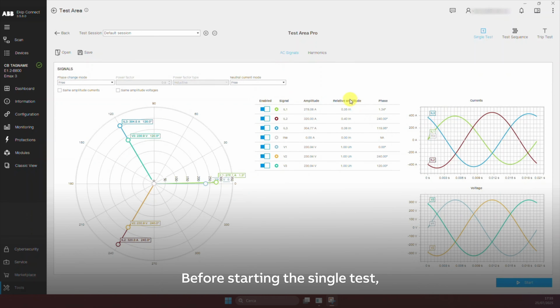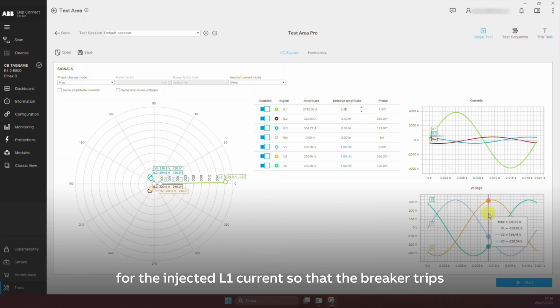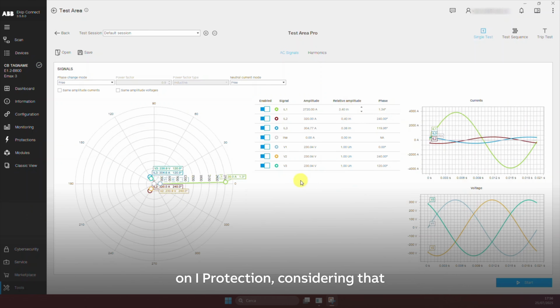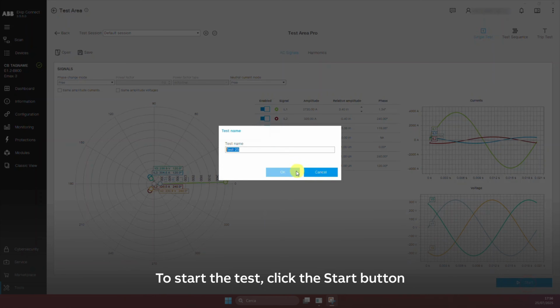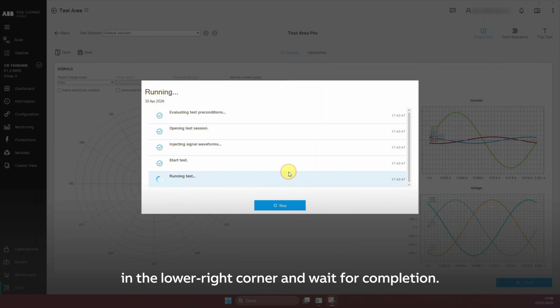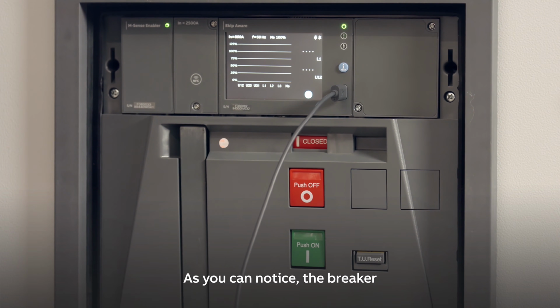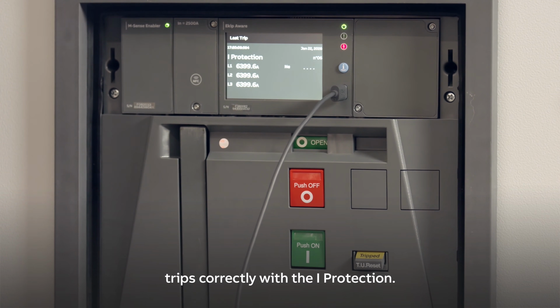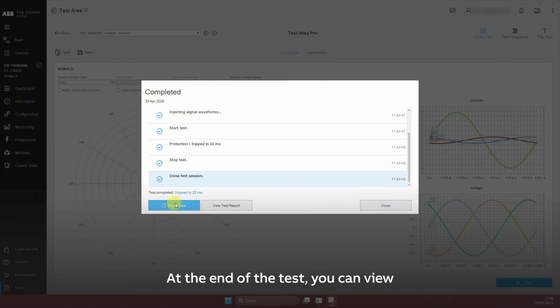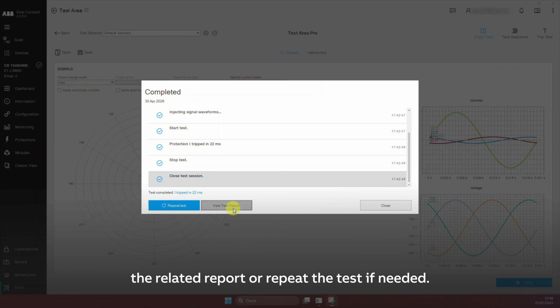Before starting the single test, we are setting a high relative amplitude of 3.4 IN for the injected L1 current so that the breaker trips on I protection, considering that its threshold was set to 3 IN. To start the test, click the Start button in the lower right corner and wait for completion. As you can notice, the breaker trips correctly with the I protection. At the end of the test, you can view the related report or repeat the test if needed.